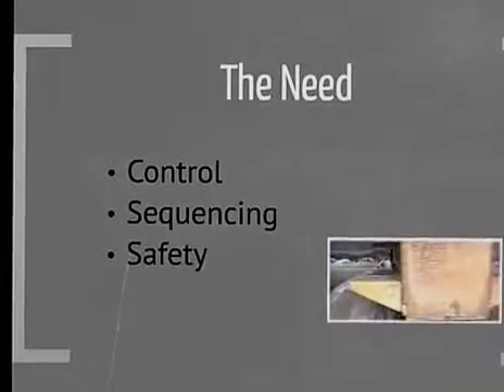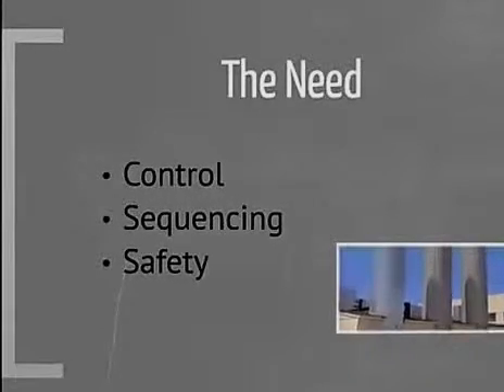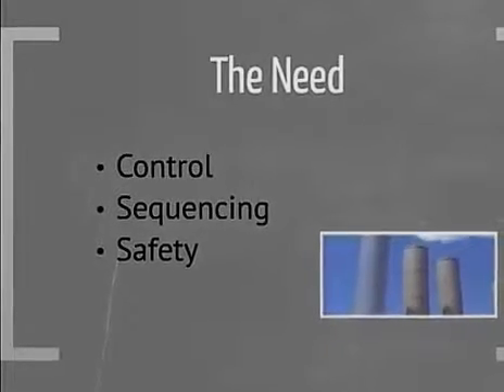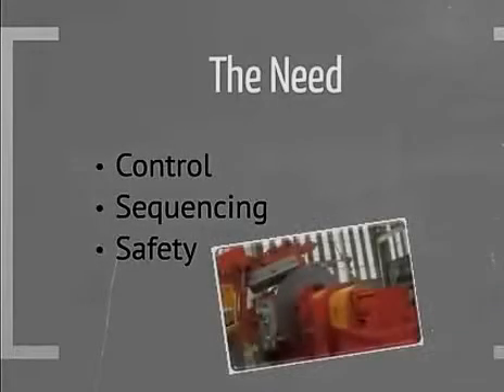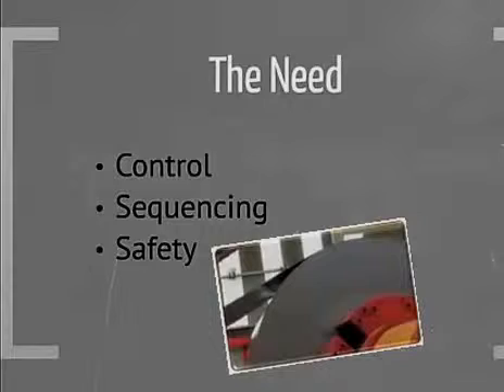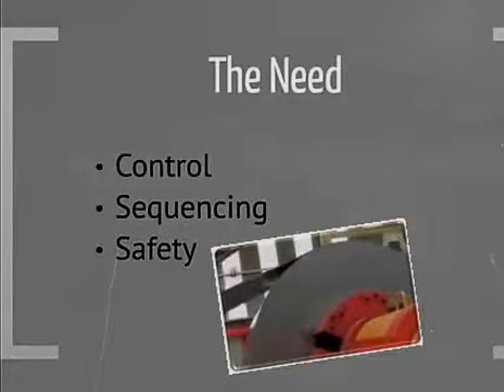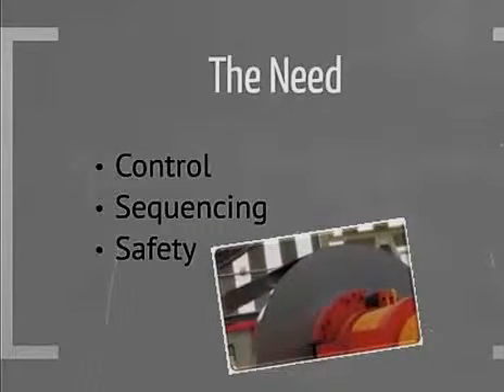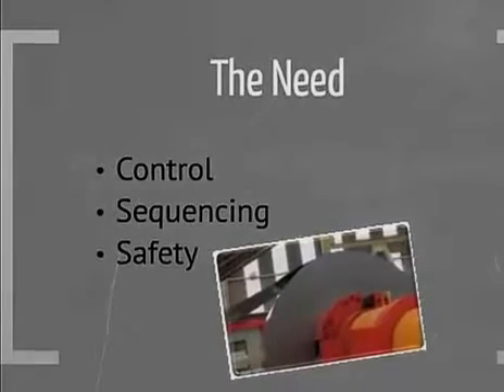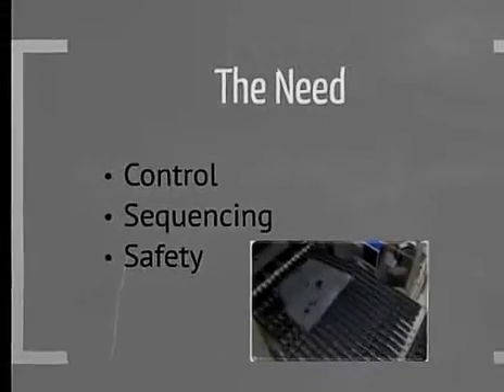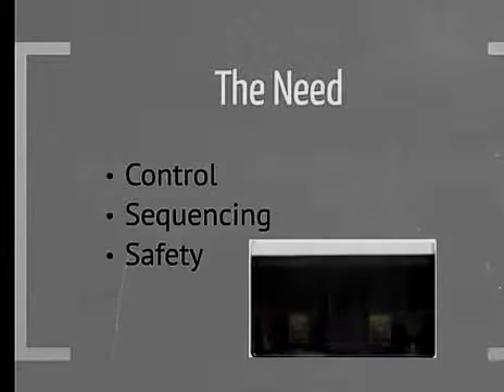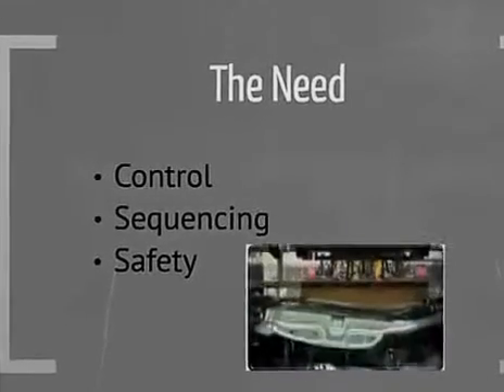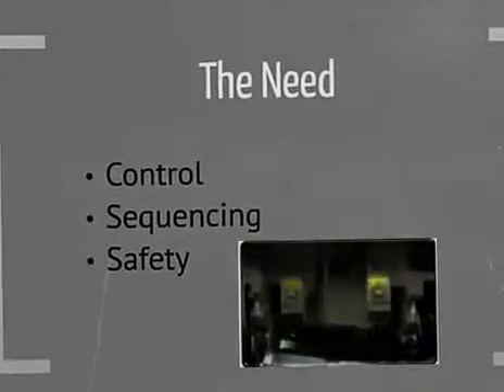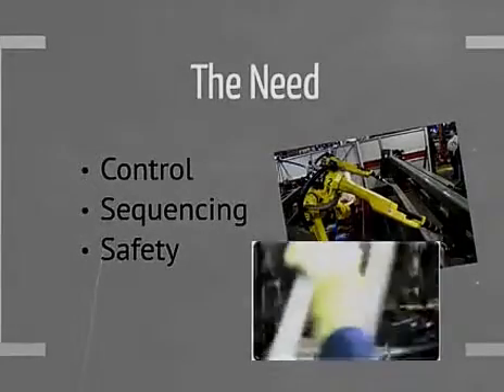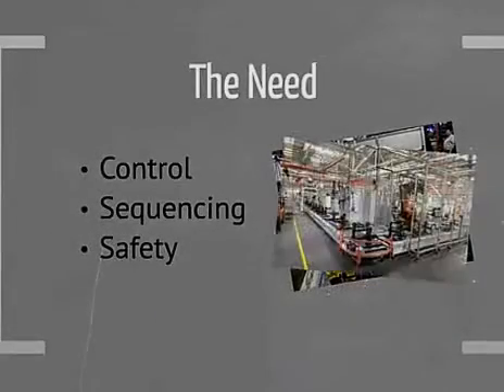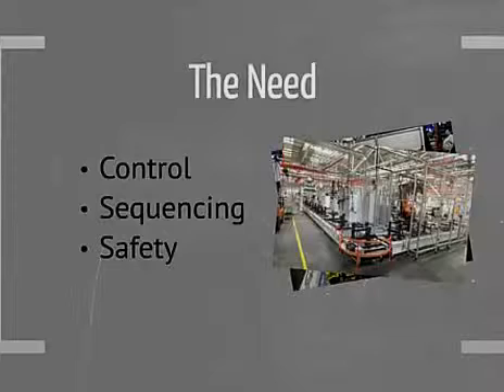PLCs run on real-time operating systems which respond to input conditions within rigidly defined intervals to ensure that the intended operation will always result. Their hardware is ruggedized to reliably operate within a wide temperature range, shielded against electrical noise, and resistant to vibration and impact. Examples of production processes that are controlled using PLCs include metal machining sequences, product assembly lines, and batch chemical processes.